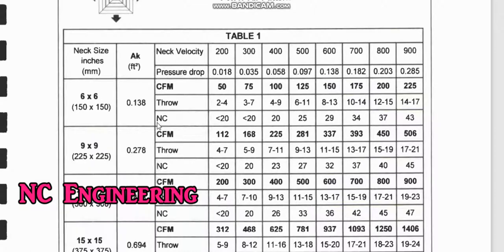Suppose we have 225 CFM and we need to select the diffuser for it. Let us start from the smallest size, the 6 by 6 inch, and see the CFM 225. When we reach 225, we see the neck velocity is going very high — 900 — and the NC level is also going up to 43.